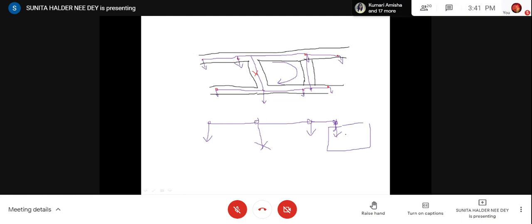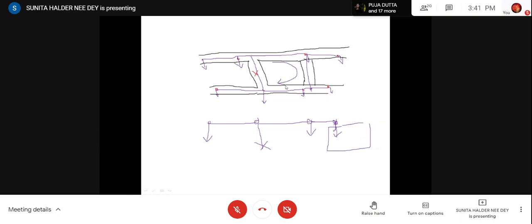Yes ma'am. Now in that case, when we are doing this distribution, we shall try to make some closed loops. It is not mandatory, sometimes it will not be possible, but if it is possible, it is better. Then voltage distribution will be better, voltage profile, voltage drop will be less, because ring main means both end feeding. For both end feeding, always the voltage drop is less.